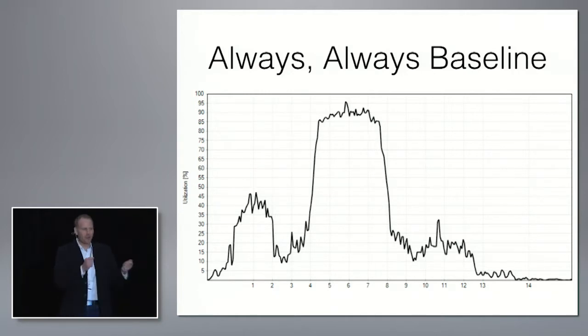And as part of doing the testing and walking around and standing there, this big piece of equipment left, got on the elevator, went down the elevator, and all of a sudden we saw the channel utilization start to go down. So ultimately what we learned, it was a portable X-ray machine that had an access point on it in workgroup bridge mode transmitting at 100 milliwatts. So needless to say, there wasn't too much communication going on on that unit, or probably the unit above and below that for this period.